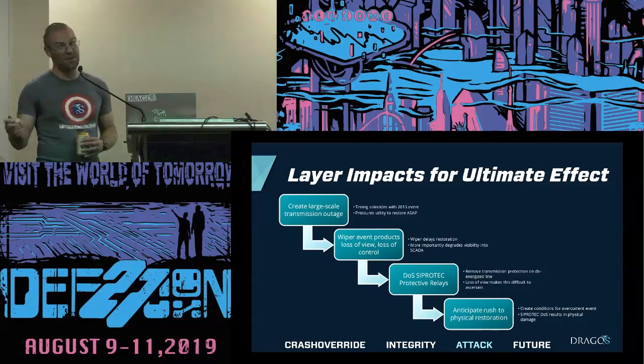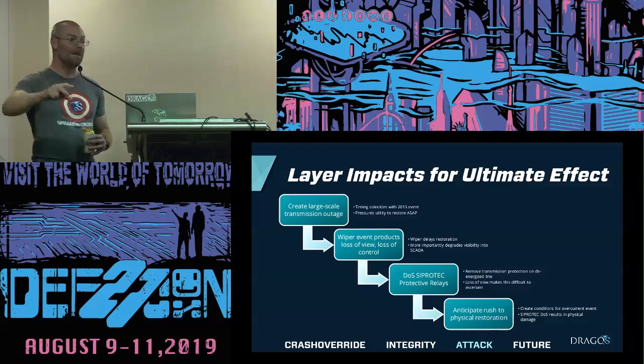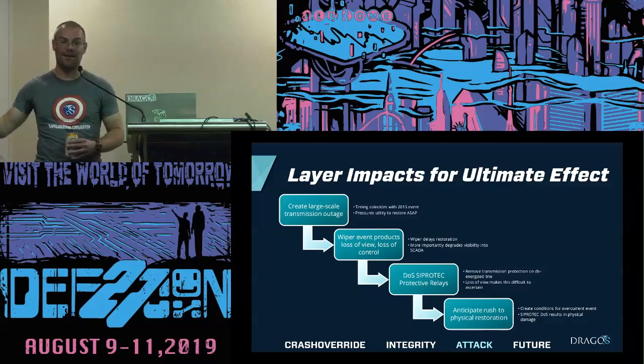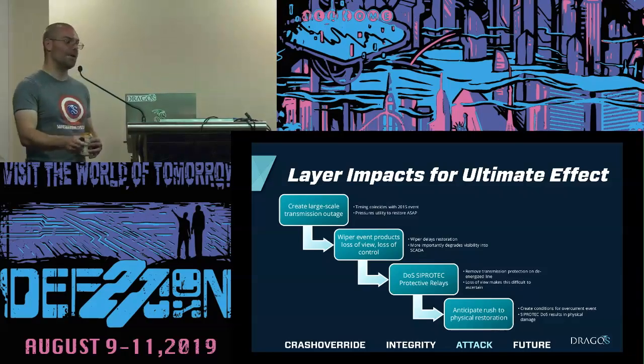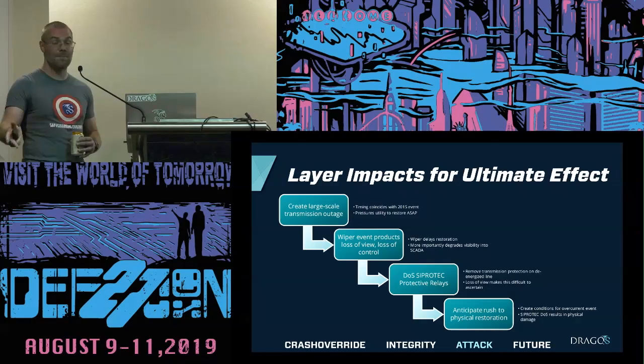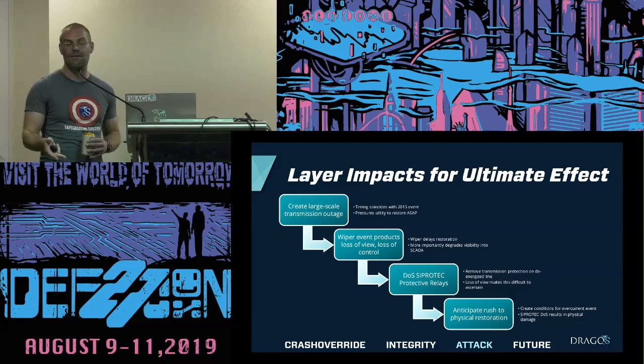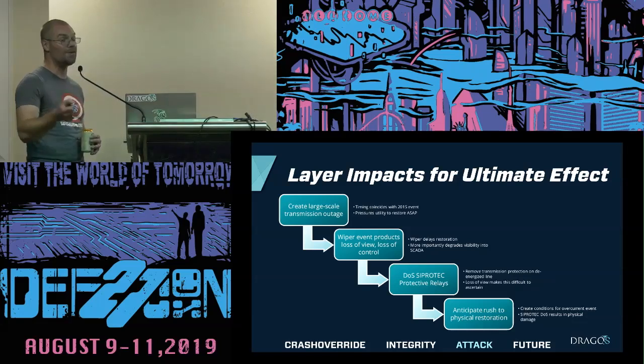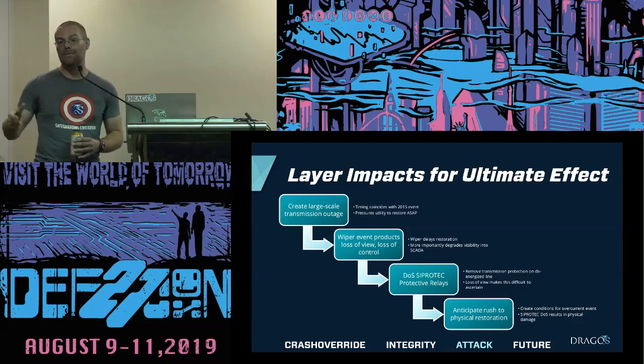An immediate potential impact of that would be an overcurrent situation—as the line is restored from a massive transmission outage across multiple sites, that line becomes so overloaded as to produce either a sag event resulting in a fault as it connects with something grounded, or overloading transformers within the transmission station that produces physical damage or increased wear and tear, leading up to physical damage.